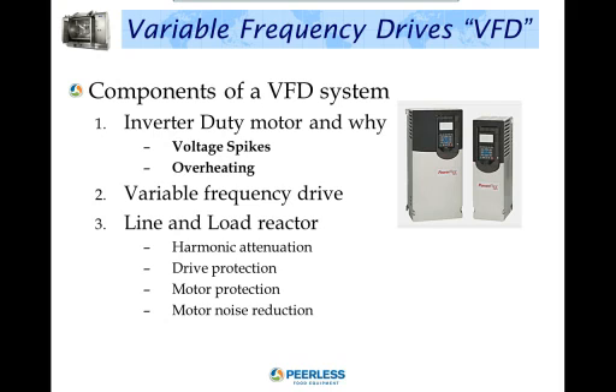A line reactor can also filter out pulsed and notched distortion, which can minimize interference with other electronic equipment like computers, PLCs, telecommunication systems, instrumentation, and other VFDs. The use of line and load reactors increases the reliability, performance, and efficiency of a VFD system. It extends the life of both drives and motors and reduces the amount of energy consumed by the motor/drive system.